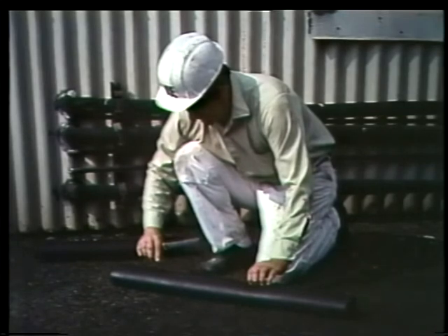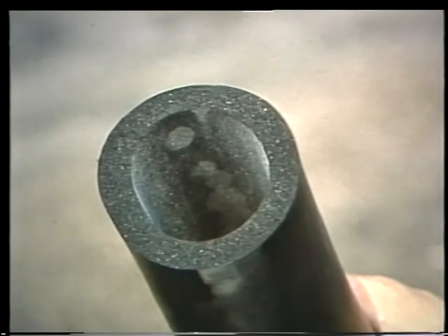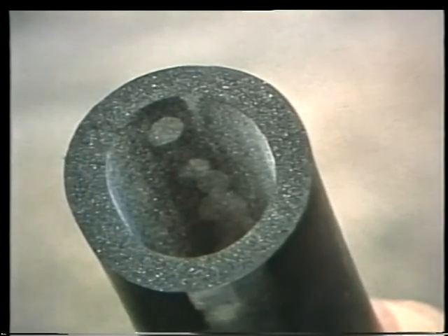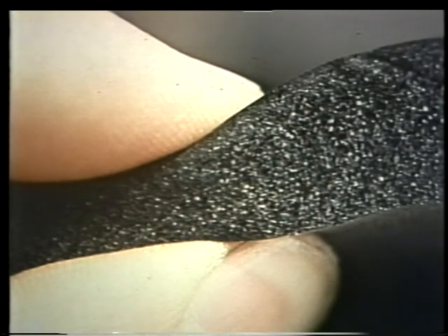Let's move on now and take a look at some kinds of insulation that are used especially for low temperatures: cellular rubber and plastic foam. Cellular rubber and plastic foam insulation come in tubular sections for insulating chilled water or refrigerant lines. They also come in blocks and sheets for special applications. The material is filled with thousands of tiny bubbles that act as dead airspace between the pipe and the outside air. Cellular rubber is made with closed cells.